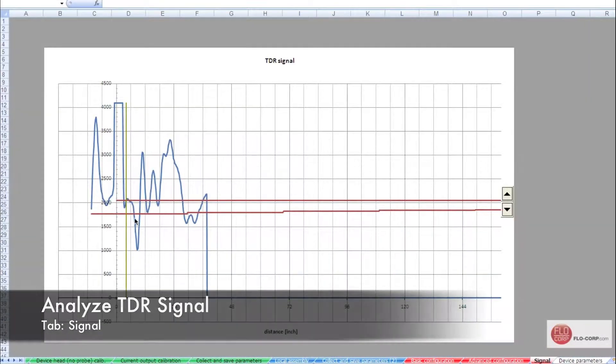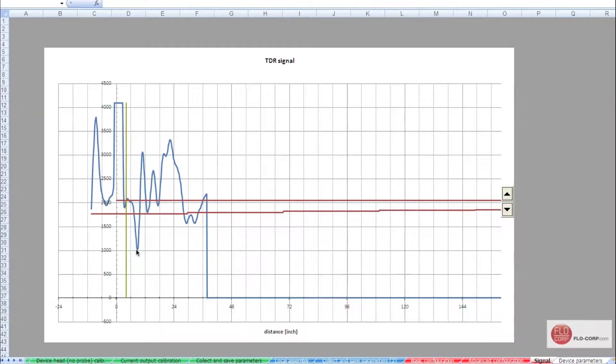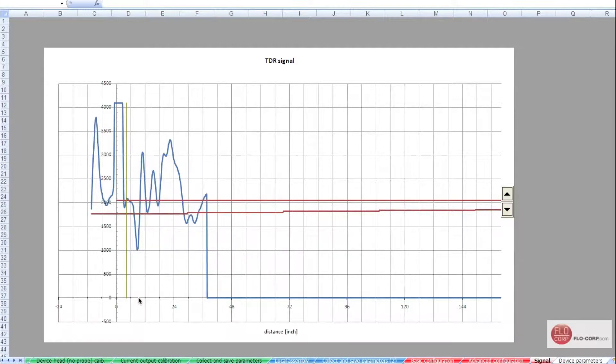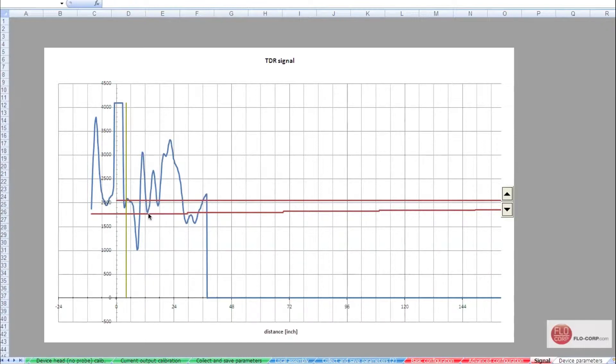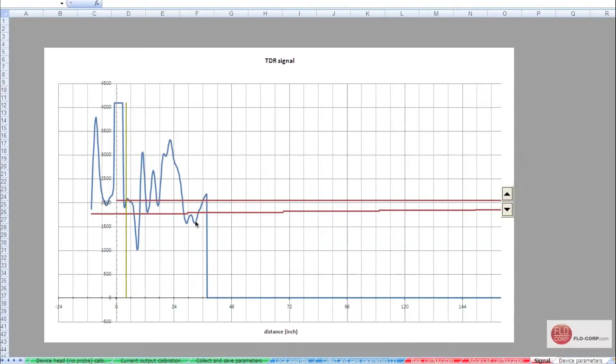This signal is a negative pulse, which is indicative of level. This negative peak is at approximately 9 inches. So we have 9 inches of level on this probe. We also have some slight disturbances in this process, as indicated by these positive pulses. We can also analyze that these negative pulses is where the probe end is, and then our signal begins to fade out.